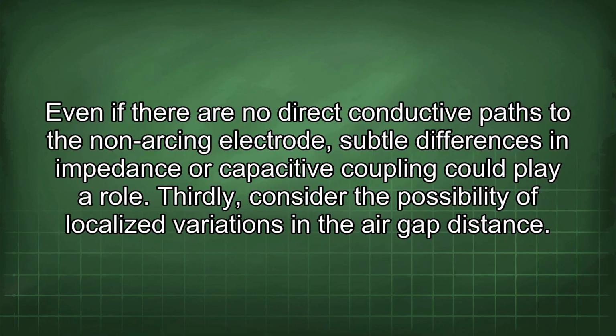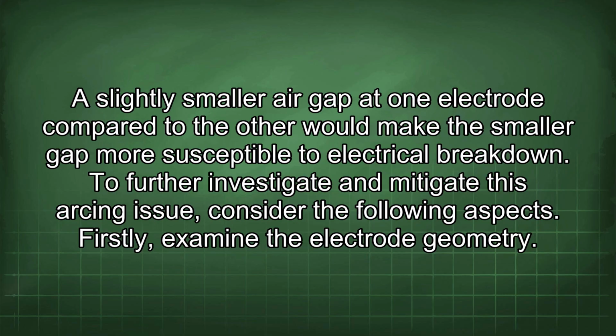Even if there are no direct conductive paths to the non-arcing electrode, subtle differences in impedance or capacitive coupling could play a role. Thirdly, consider the possibility of localized variations in the air gap distance. A slightly smaller air gap at one electrode compared to the other would make the smaller gap more susceptible to electrical breakdown. To further investigate and mitigate this arcing issue, consider the following aspects.